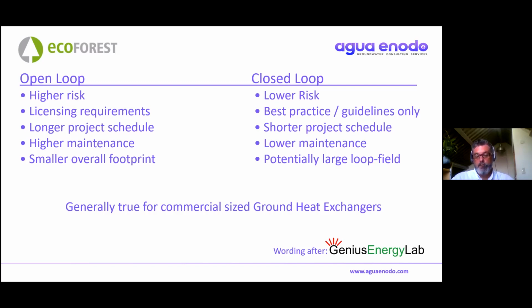The footprint of the installation would depend on the size and balance of the loads, but generally an open loop system would have a smaller overall footprint. Here I'm not talking about single domestic systems, but larger commercial systems. That's because once we've installed the abstraction and injection well, we can put that in a basement or a trafficable manhole cover - it can be subsurface, essentially with a very small footprint.